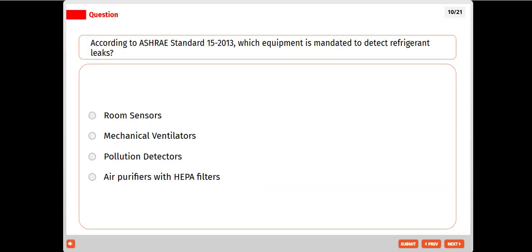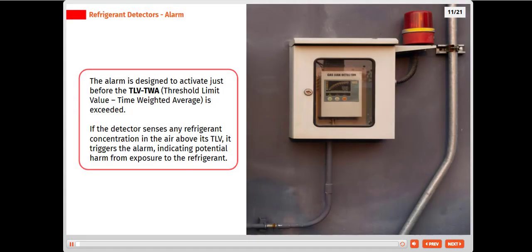According to ASHRAE Standard 15, 2013, which equipment is mandated to detect refrigerant leak? Room sensor, mechanical ventilation, pollution detector, air purifier with HEPA filter. Which equipment is mandated to detect refrigerant leak? Room sensor. The alarm is designed to activate just before the threshold limit value, time-weighted average, is exceeded.